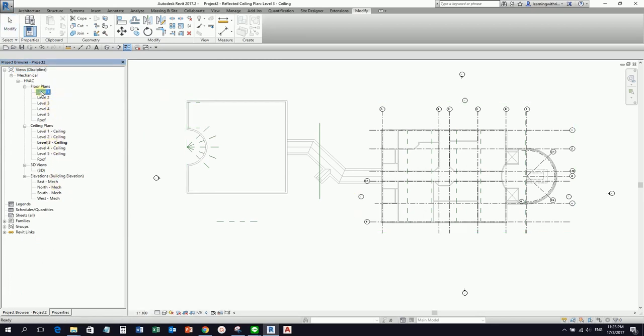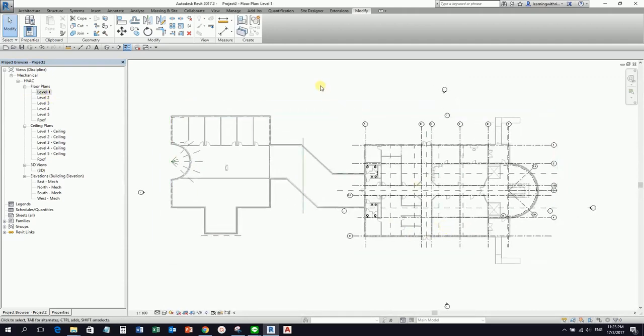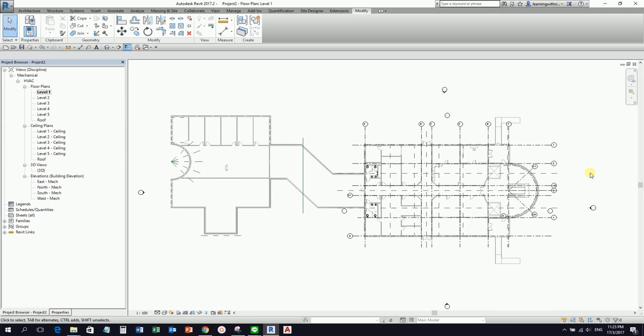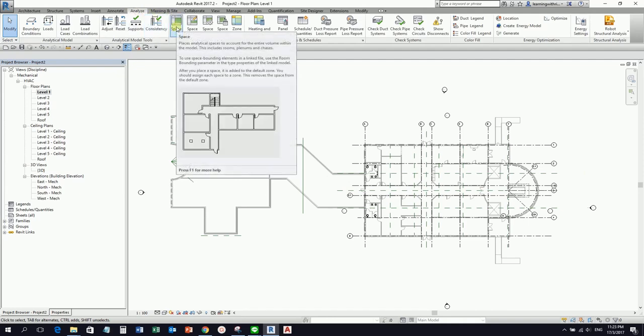Now I'll open Level 1 and create the spaces. From the Analyze tab you can find the Space tool. We need spaces because if you want to do the heating and cooling loads calculation and create an analytical model of your project, you need to add spaces. Space places analytical spaces to account for the entire volume within the model, including rooms, plenums, and chases.